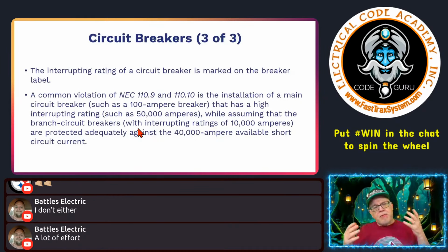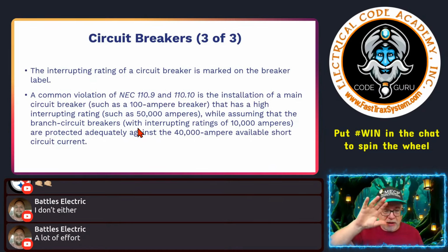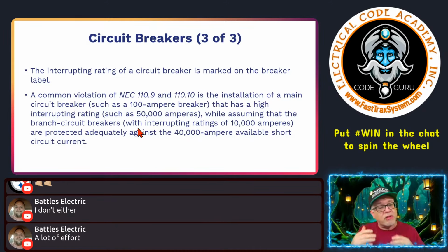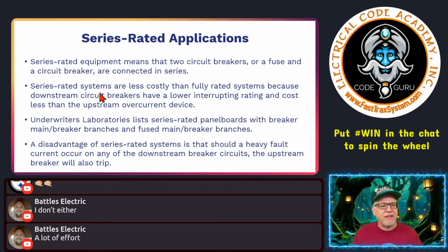So residential, around the country they pretty much tell you that the residential utility is not going to exceed 10,000. So most of the main breakers are 22,000. Okay, so that is going to be that level. And they're designed to work in series with the breakers that are in the panel that are made for that panel board. And those are typically going to be less, usually 10,000 or something marked on. Okay, that's okay. It's the way it's designed. And that gets us into what we're going to talk about, series rated.